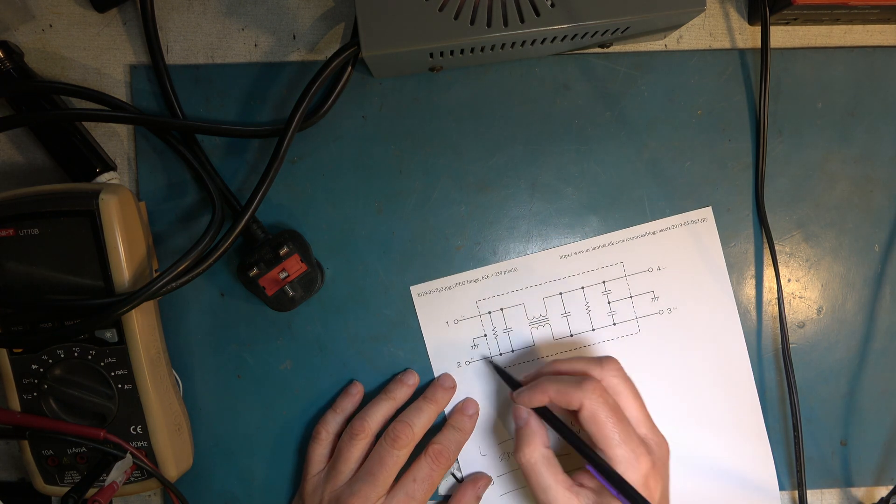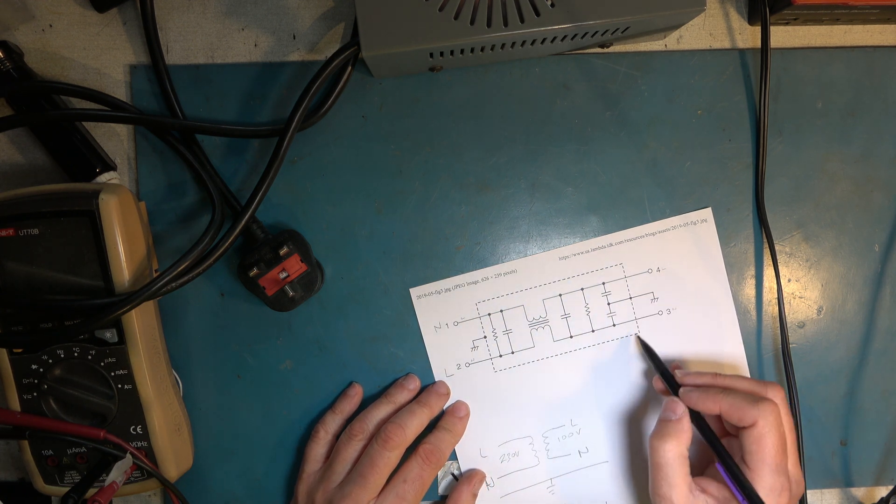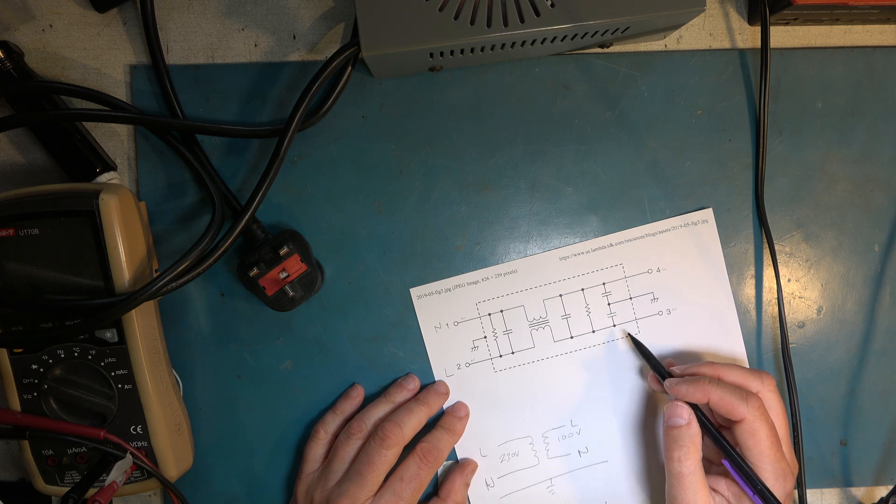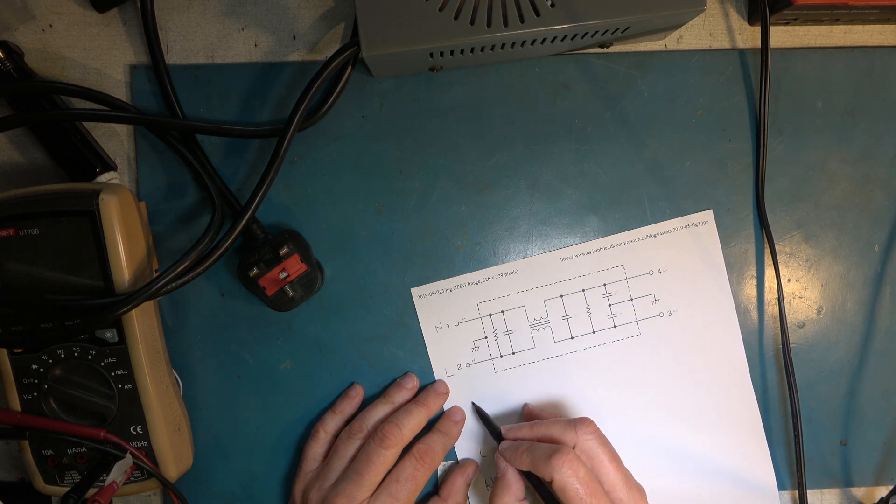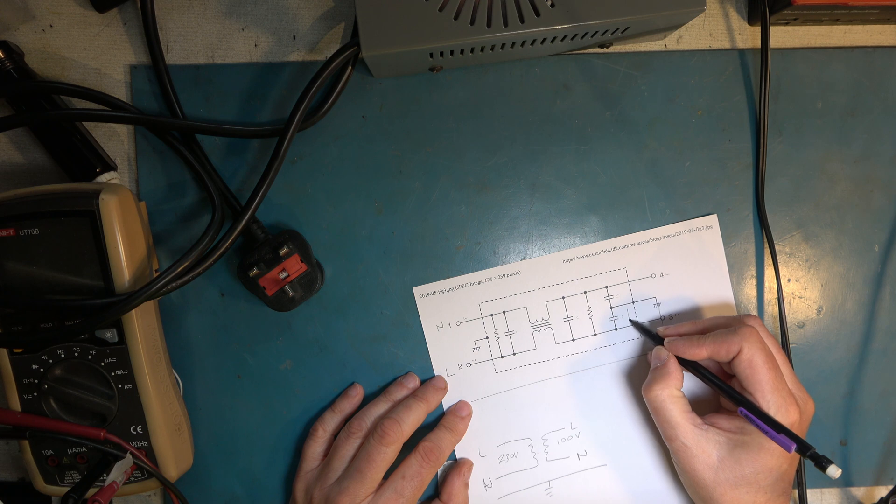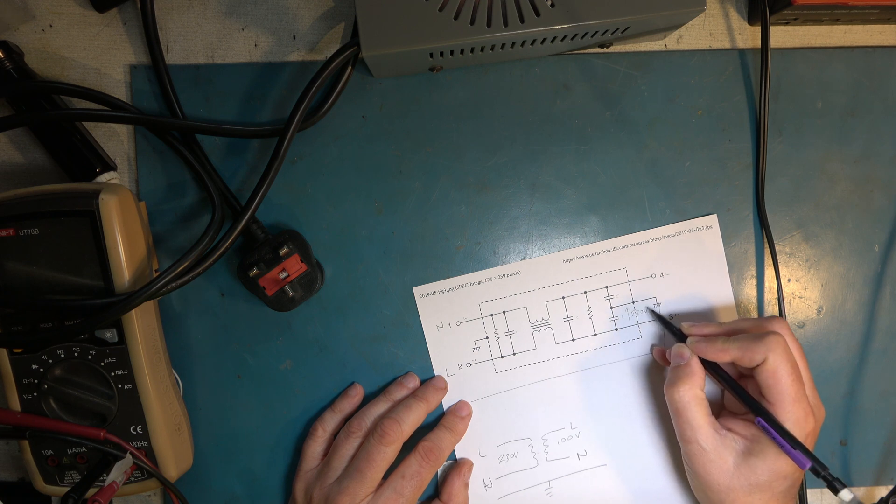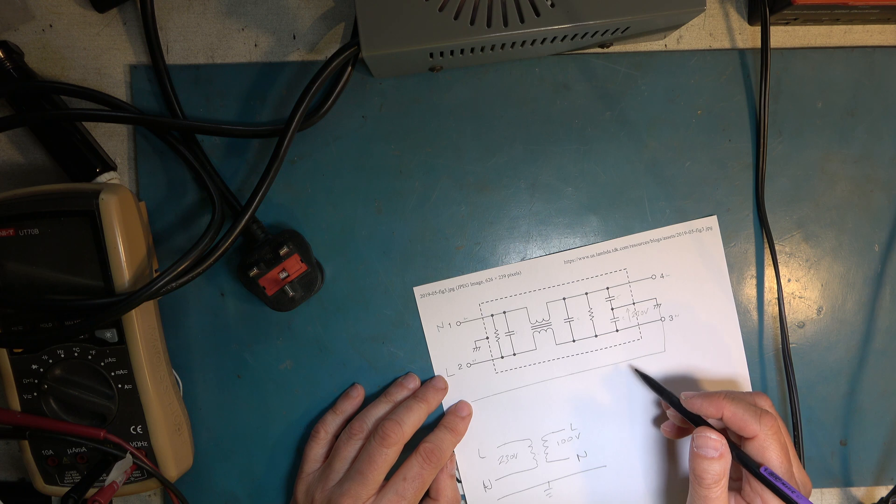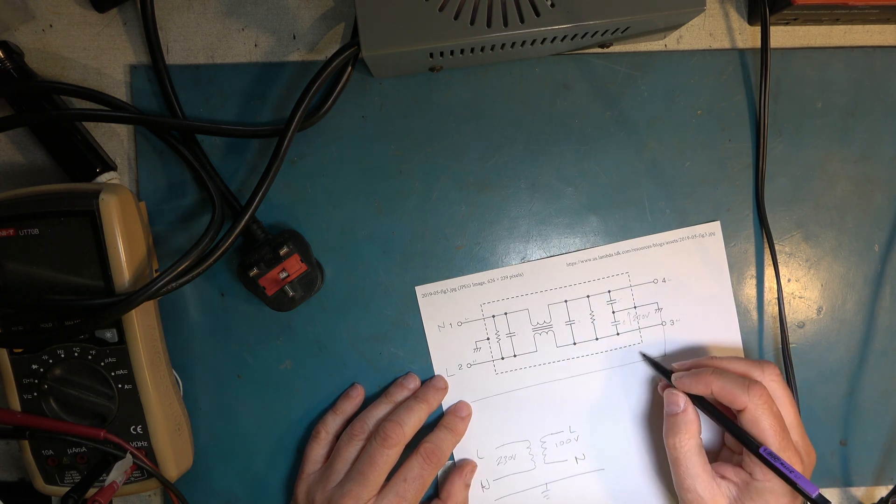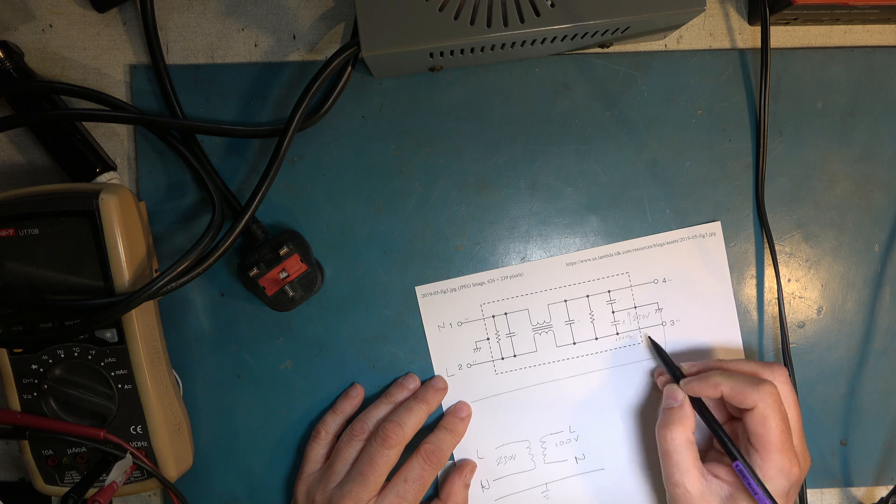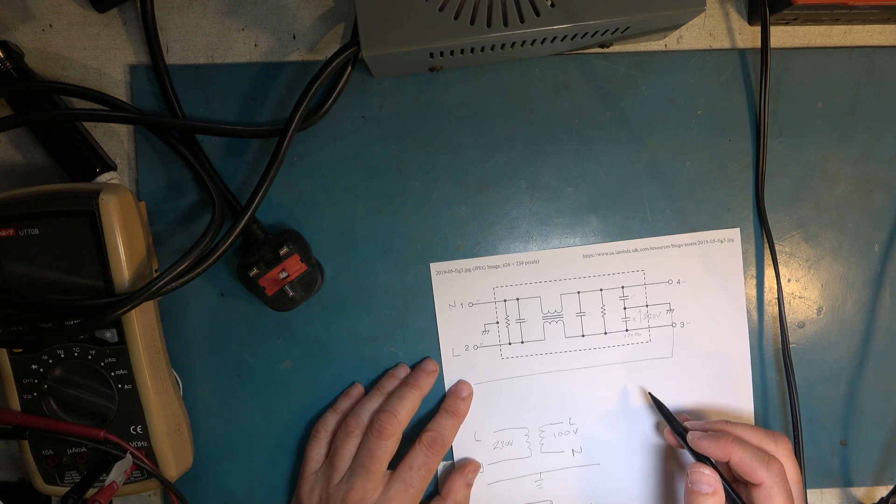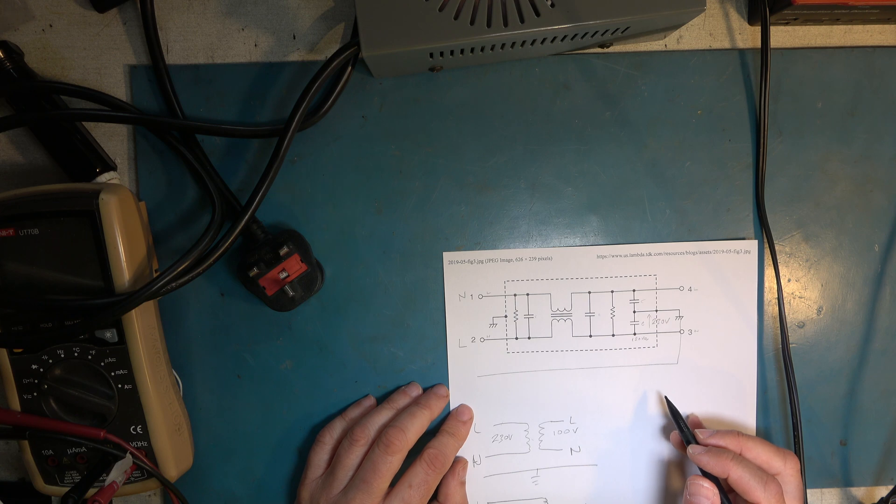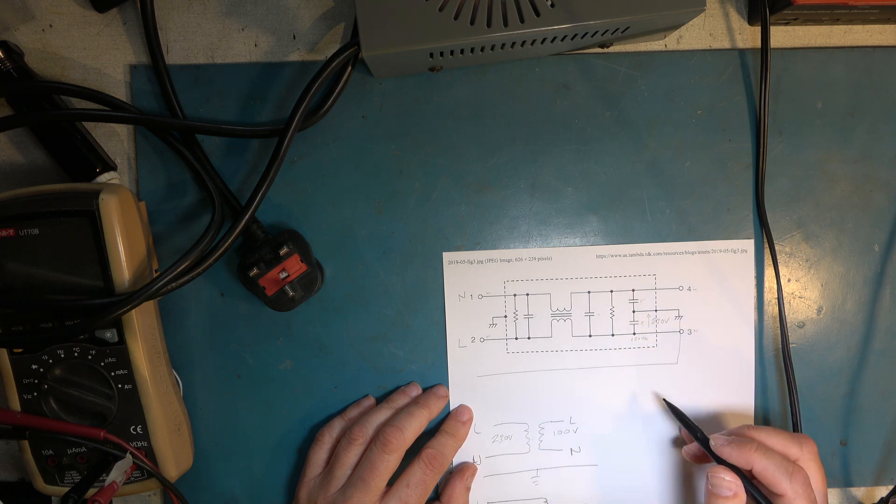And in our piece of equipment, we have a filter, an RFI filter, and these are capacitors here. Now, our earth condition now, here, has 230 volts AC across this capacitor. But this was a piece of equipment that was originally designed to work on 100 volts or 110 volts. And so, very likely, that filter capacitor is only rated at maybe 120 volts AC or similar. And it's now got UK mains across it. And it's going to protest with a large cloud of smoke and potentially hotness. Because you could have a fire, you could have a dangerous situation here with this capacitor that's been overloaded.